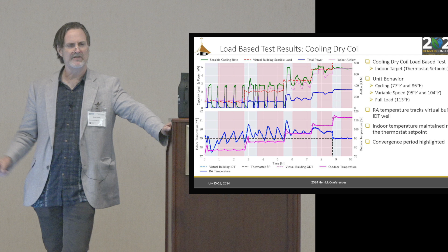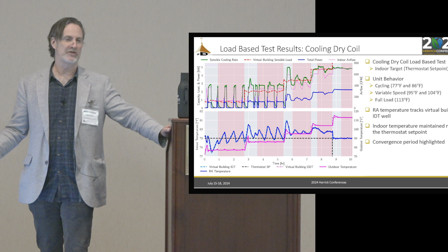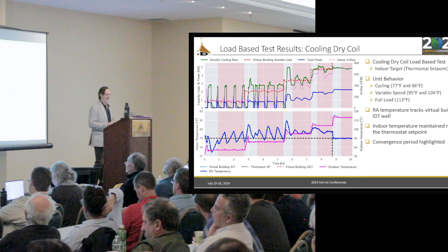In the second to last segment, you can see it's still modulating, but it's pretty close to the very top of its input power and its capacity. And at the 113-degree point, there's nothing here that shows this, but that was converted to a full load test, and that's just the maximum capacity that it can produce. All right, I'm not going to spend more time on how that works, but that's the sort of technical stuff of how the test process works.